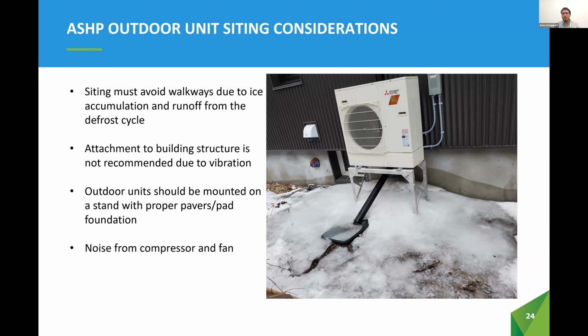Outdoor unit fans are typically in a horizontal orientation, which differs from the vertical orientation of traditional AC systems. Barriers such as fences, hedges, and garden sheds, as well as add-on features such as blankets or acoustic enclosures, can offer some mitigation for noise. In addition, quality outdoor units also offer low noise operation modes.